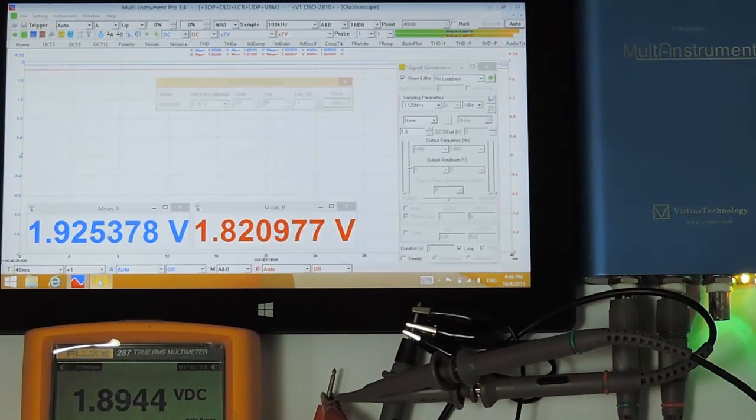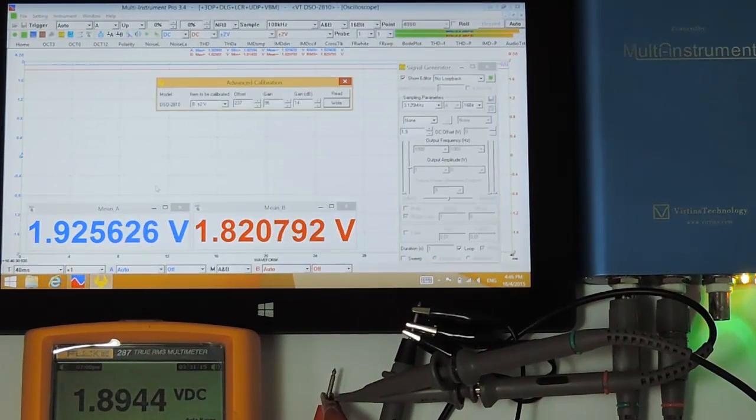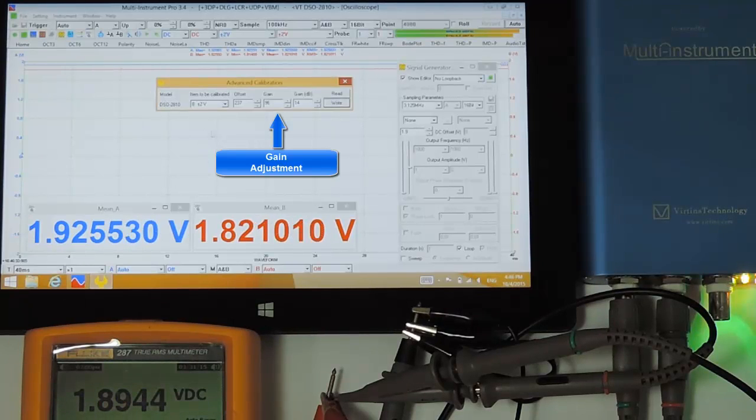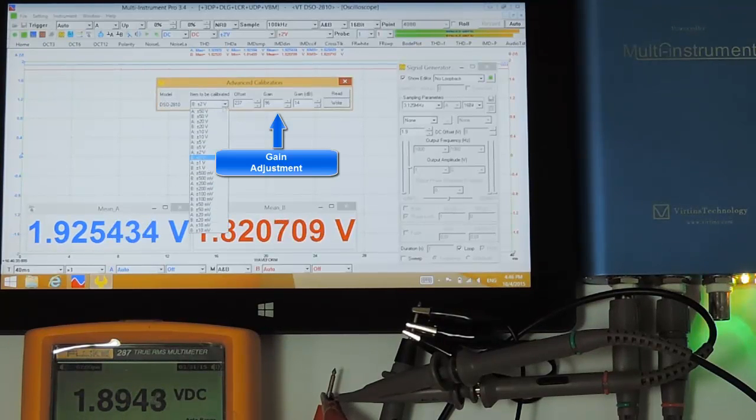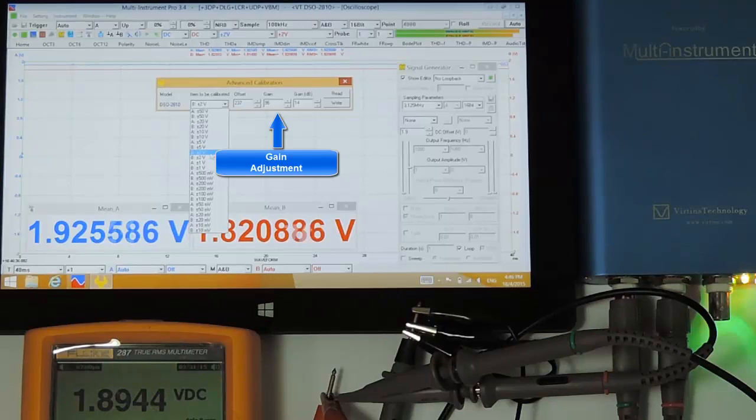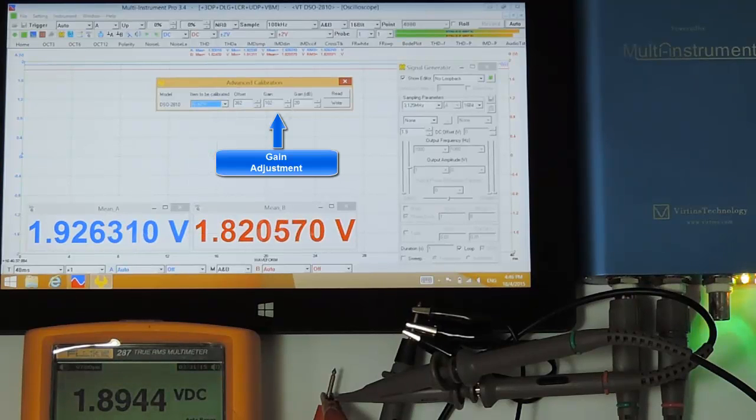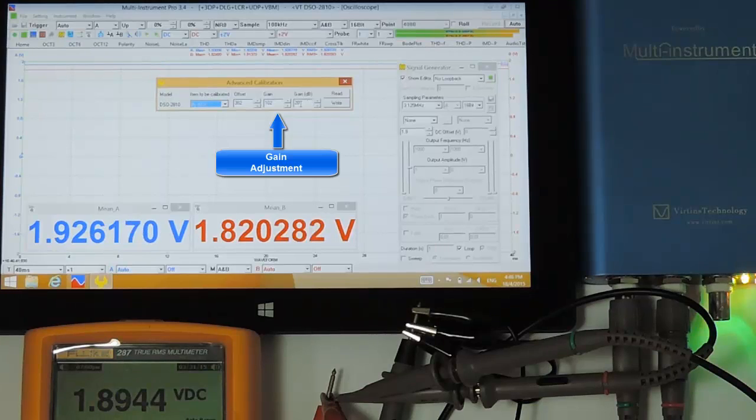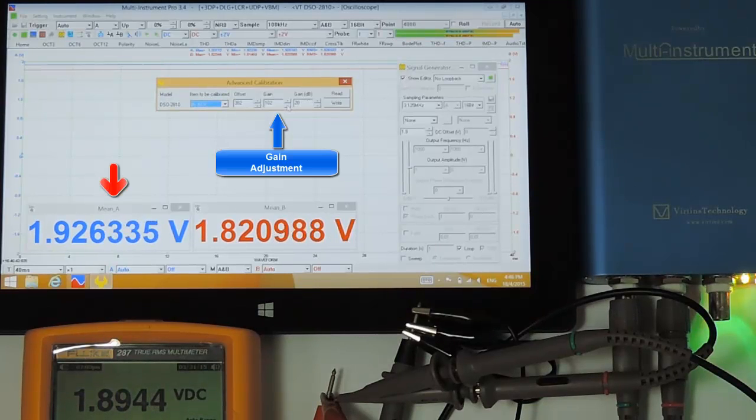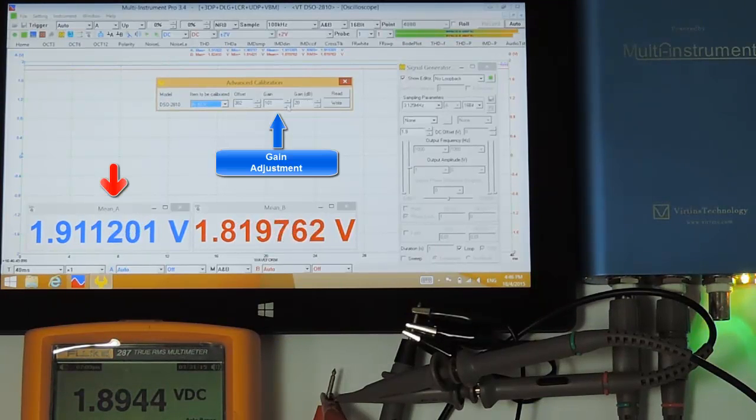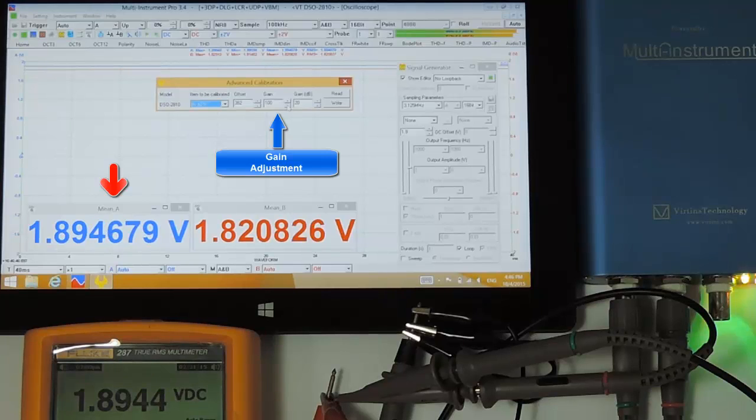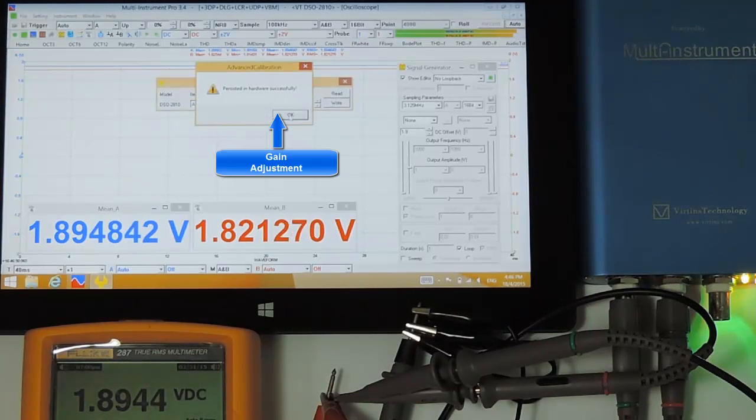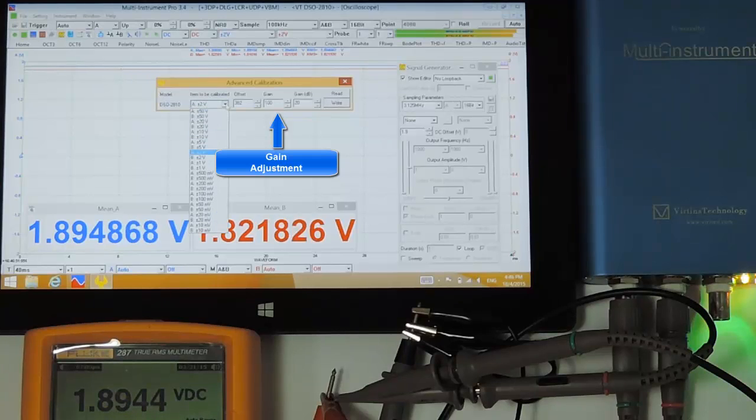There are two gain adjustment boxes. Generally, the gain box provides finer adjustment than gain dB box. Select channel A and adjust the gain box. Okay, this is the closest value we can get. Persist the changes in the hardware.